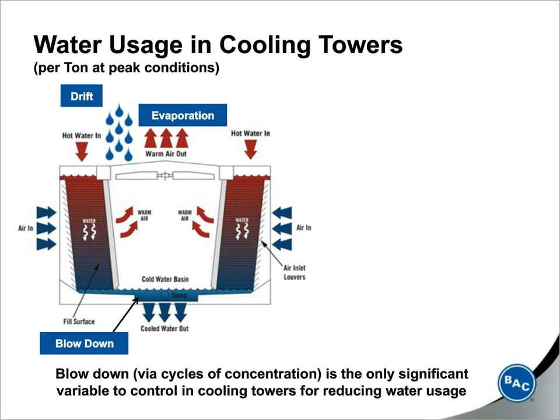Now that I've gone through the material of construction options, let's talk about how we can save water. The two main components of water consumption in a cooling tower are evaporation and blowdown. And they're shown here on this tower graphic. Evaporation is the driver for evaporative cooling, so it's always going to occur, and it's always going to be a function of the building heat load that's sent to the tower. So the evaporation, it is what it is.